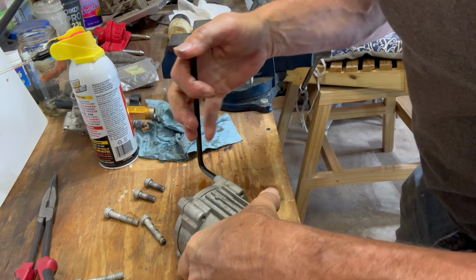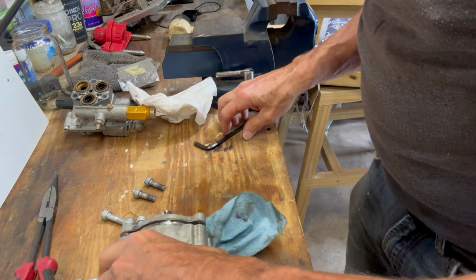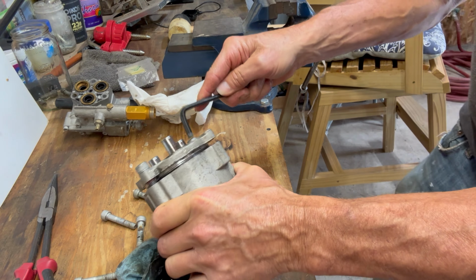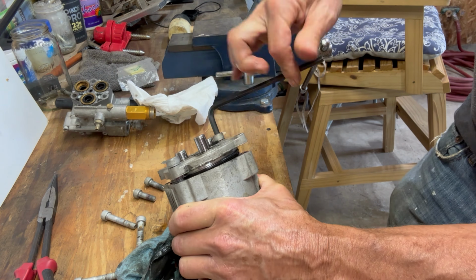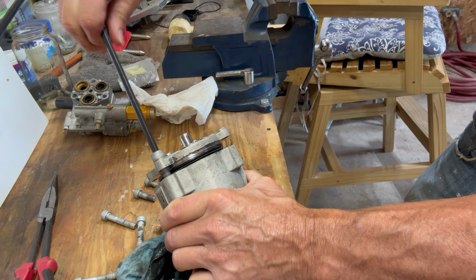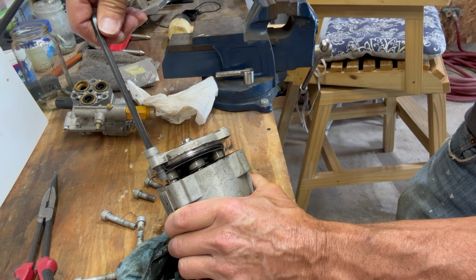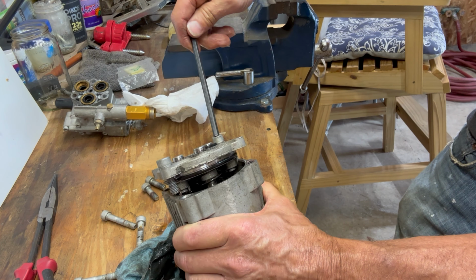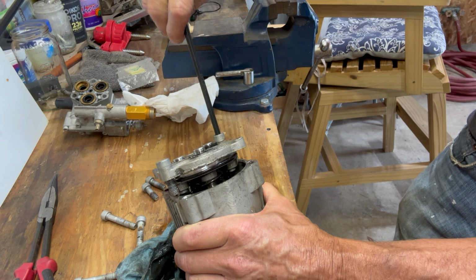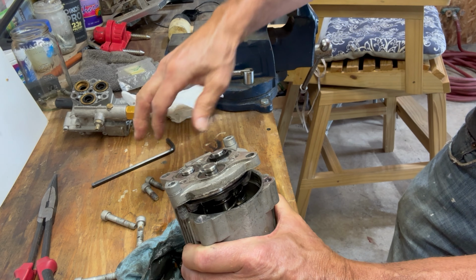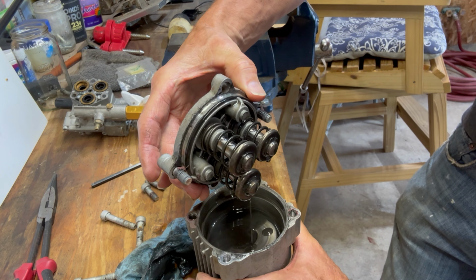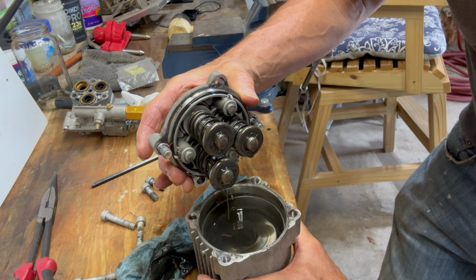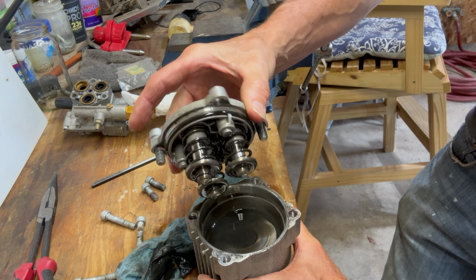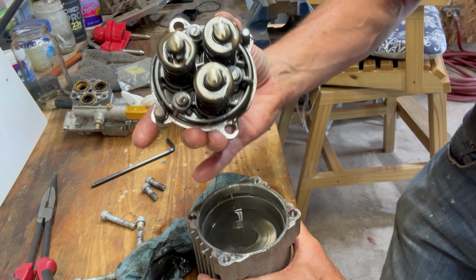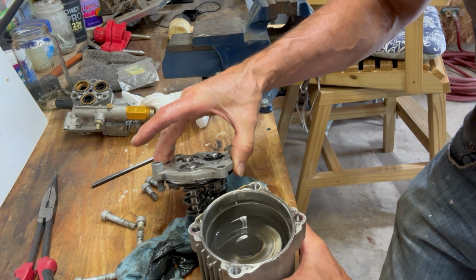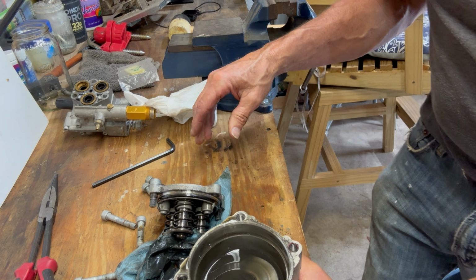Oh, it's turning. Got oil. It's got oil. Let's turn this thing. There we are. The pump oil level is surprisingly low, but relatively clean. But the drive shaft, swash plate, thrust bearing, ball bearings, oil seals, they all look to be clean and free of any damage.